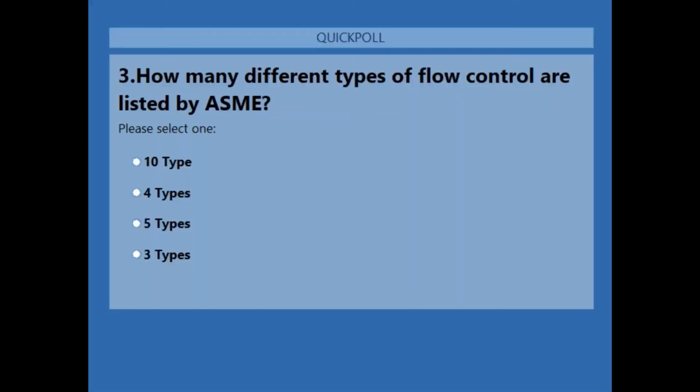Perfect. And so the other question we had was in regards to the flow control and venting. Does our flow control need to be vented, given that it's an internal type flow control? Great question. Ours does not need to be vented. There needs to be a vent after the interceptor. That's for everybody. But with our Schier interceptor, since we're certified with a built-in flow control, we do not need a vent on the inlet side of the interceptor.